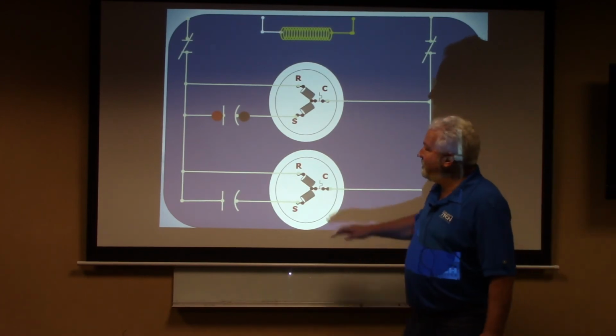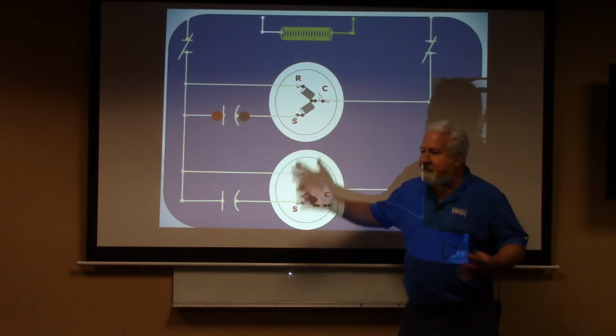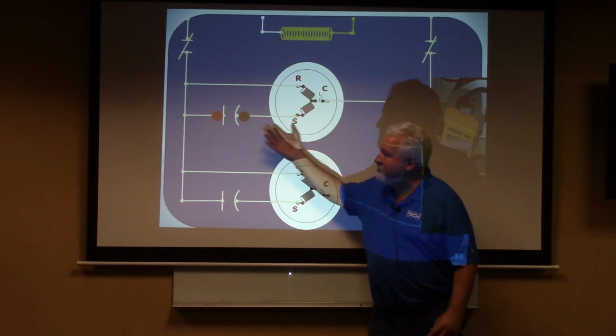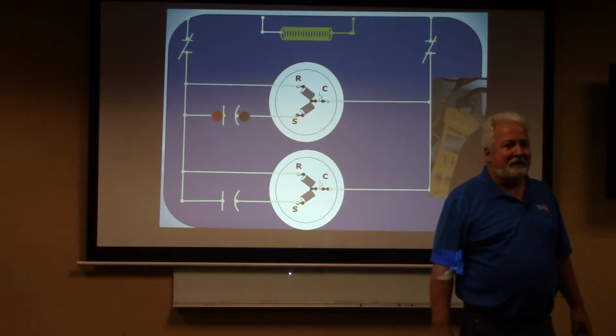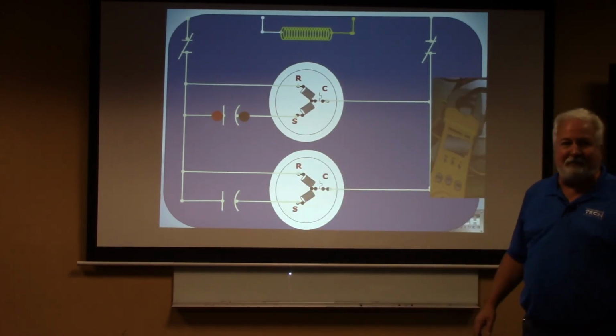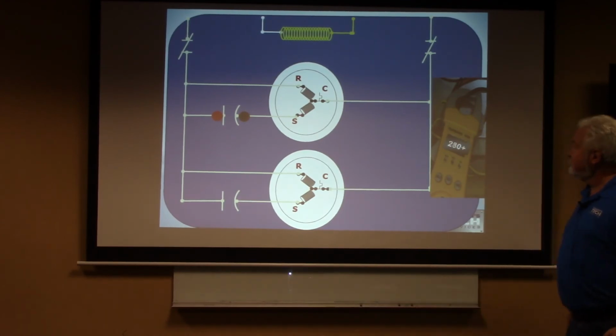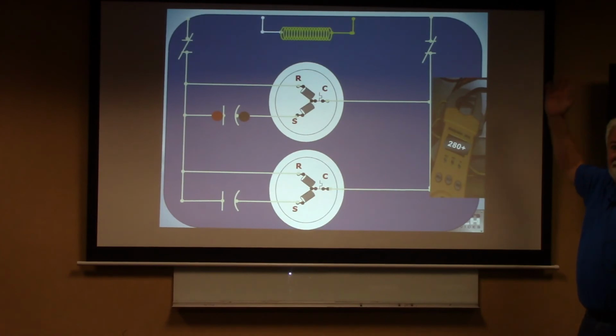I usually get 240 out of that one. Yeah, that's going to see back EMF. I'm going to read that generated voltage coming back off of that start winding right there. It might be 370, might be 390. Is that right? Sweet. Good. There it is. So it's 280 plus. Good. All right. Let's look at here and here.